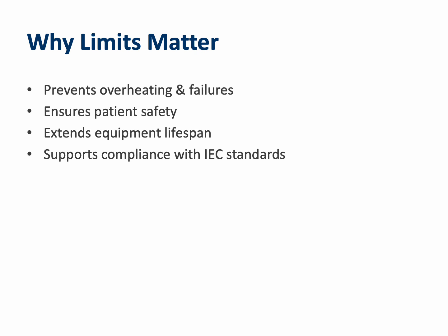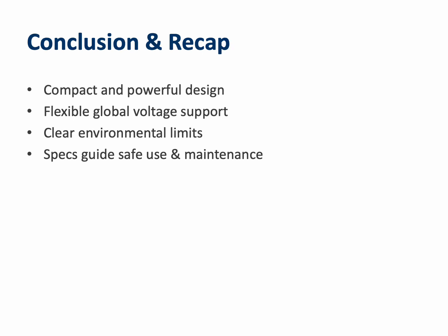Respecting the FT10's environmental and power limits ensures safe and reliable performance. If the device is operated outside of these boundaries, say in excessive heat or under unstable voltage, risks increase dramatically. Overheating, component failure, and even patient safety risks could arise. Staying within limits also helps extend the device's lifespan and keeps it in compliance with international standards like IEC 60601. For biomedical engineers, this is part of the everyday responsibility of ensuring both technical and clinical safety.